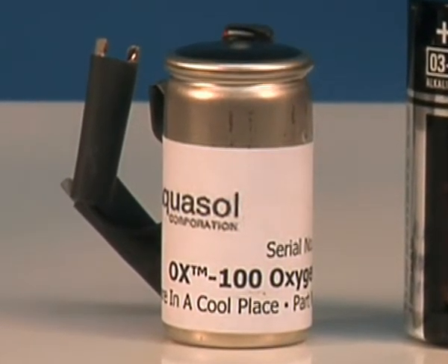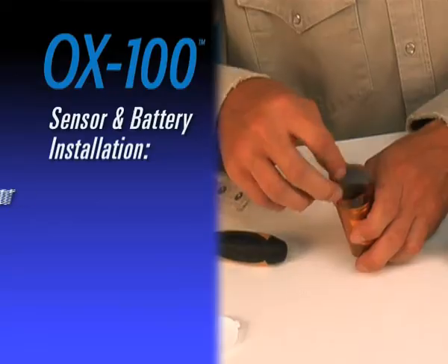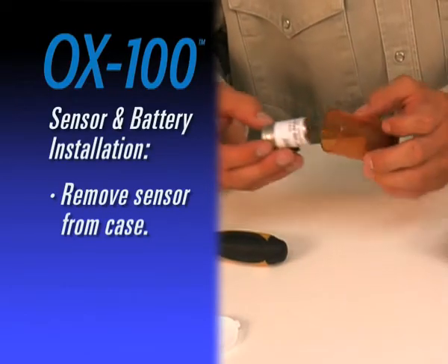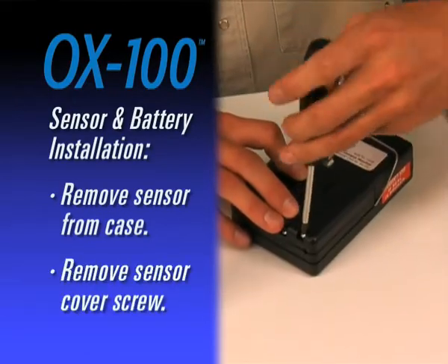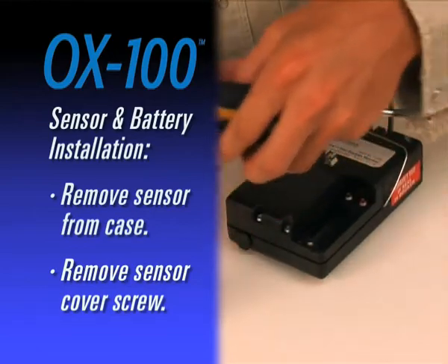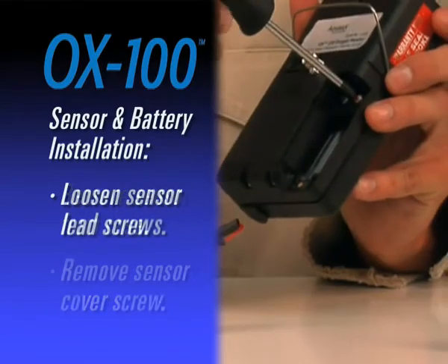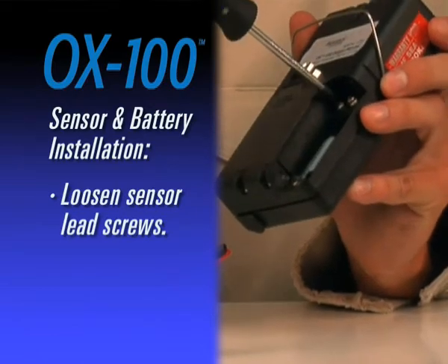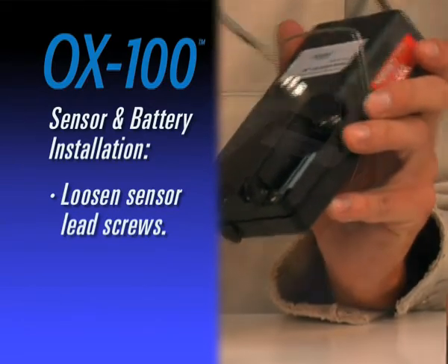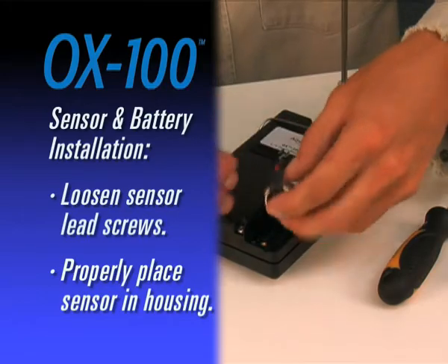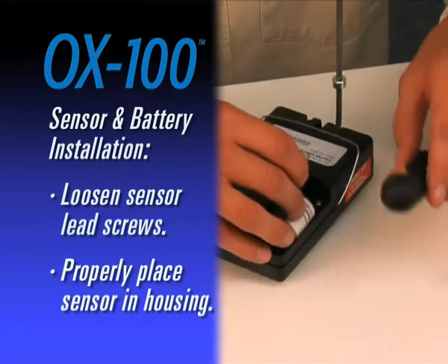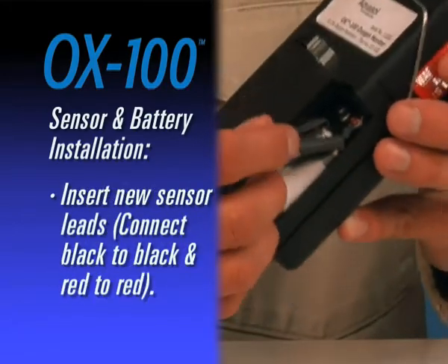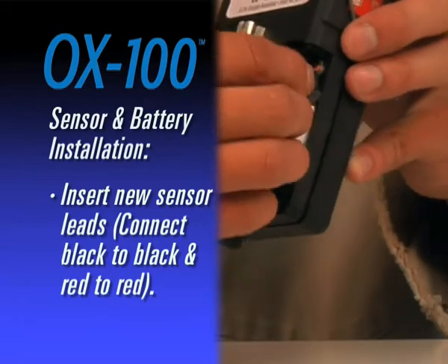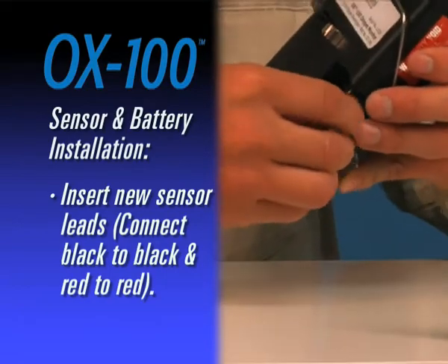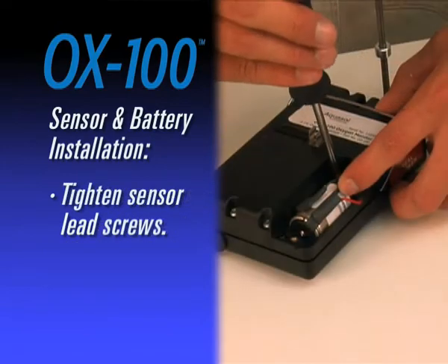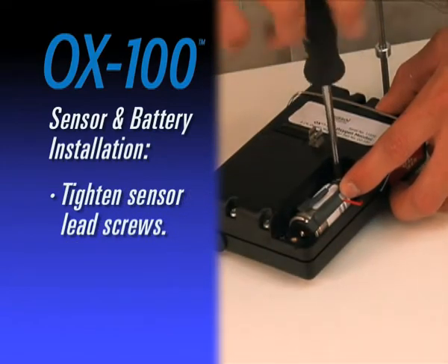To install the sensor and batteries prior to first use, remove the sensor from the protective case. Unscrew sensor cover retaining screw with a Phillips head screwdriver. Loosen black and red sensor lead screws. Place sensor in housing with plain end up and sensing end down. Insert new sensor leads connecting black to black and red to red. Tighten black and red sensor lead screws.